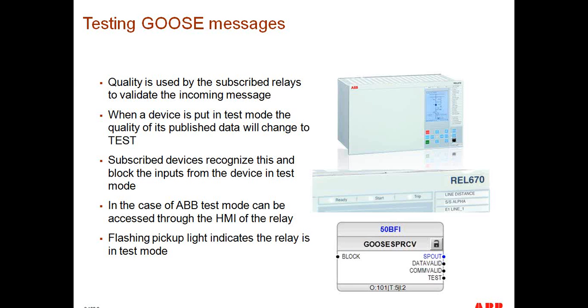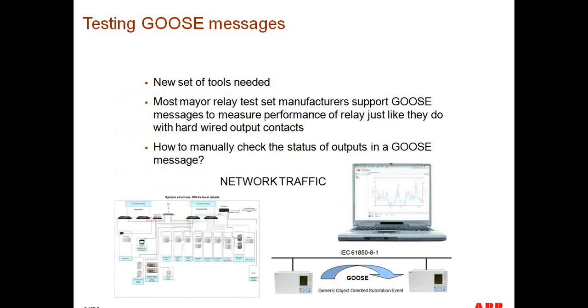But the key is this: quality has to be used to indicate that a particular device is being tested, and it is exactly the equivalent to somebody going to a panel, pulling off the test fingers, and that essentially isolates the outputs of that device that's being tested from the inputs of other devices that are still in service.